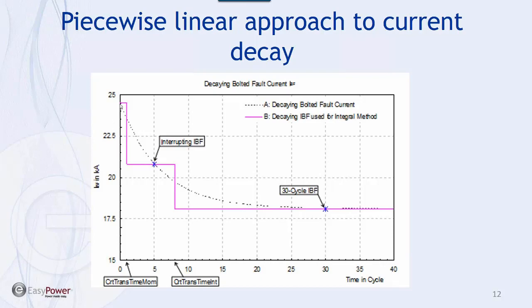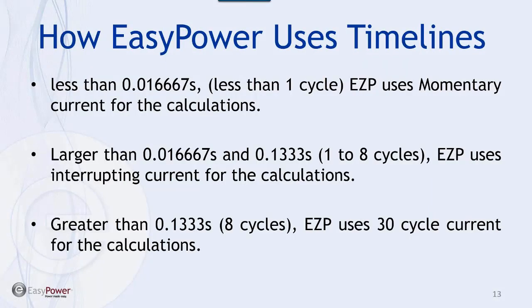But what happens is that if it has seen this current and has made it to the second round, or to the interrupting current area, there is a memory. We know that it has moved a little bit, and we keep that in memory, and we add it up here until it reaches the final distance. It passes that final point, it has traveled that distance, and it trips. That's the point where the trip device trips entirely. Now, let me just move on here. We went over these times, right?